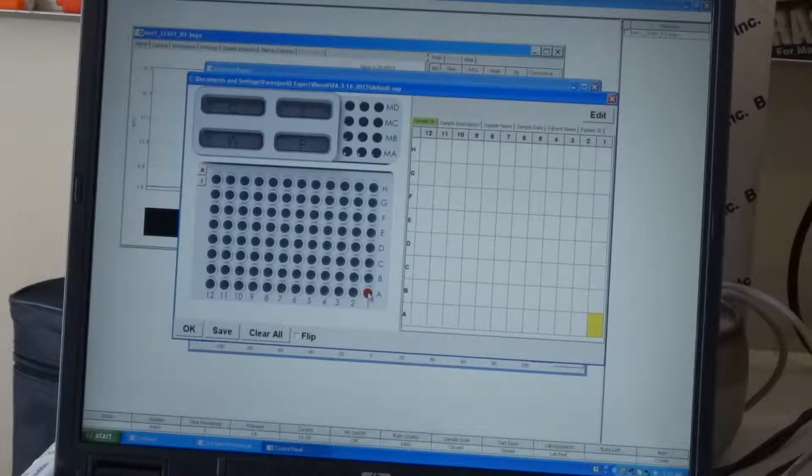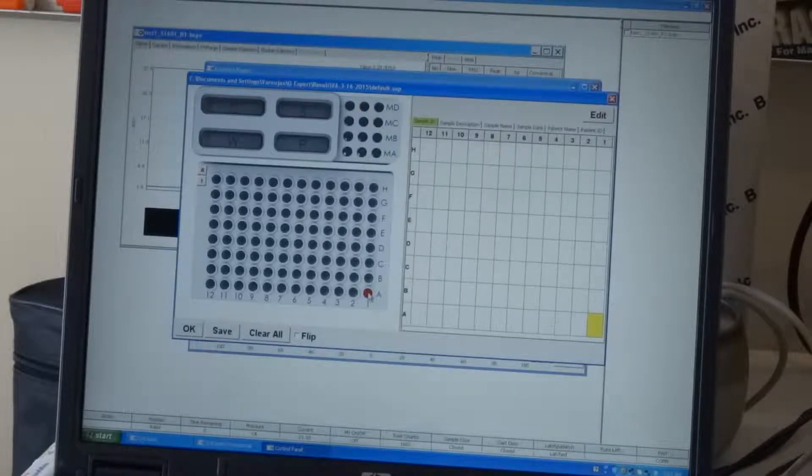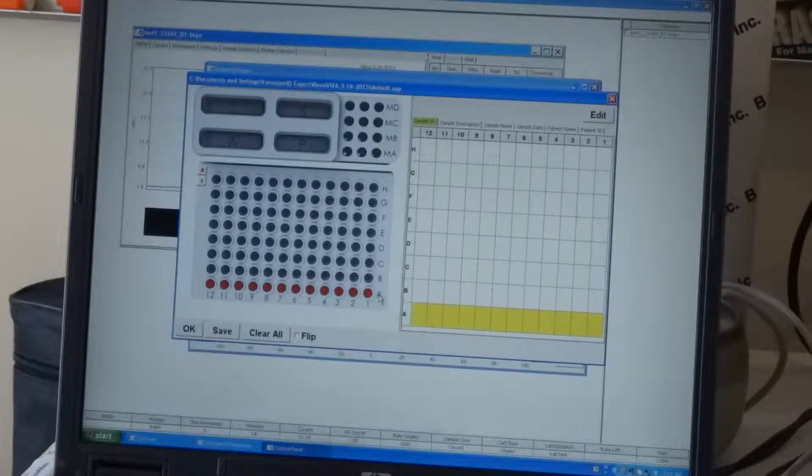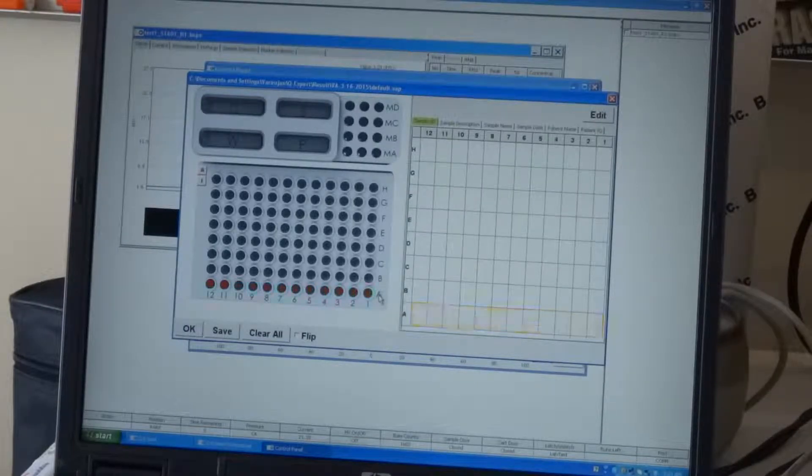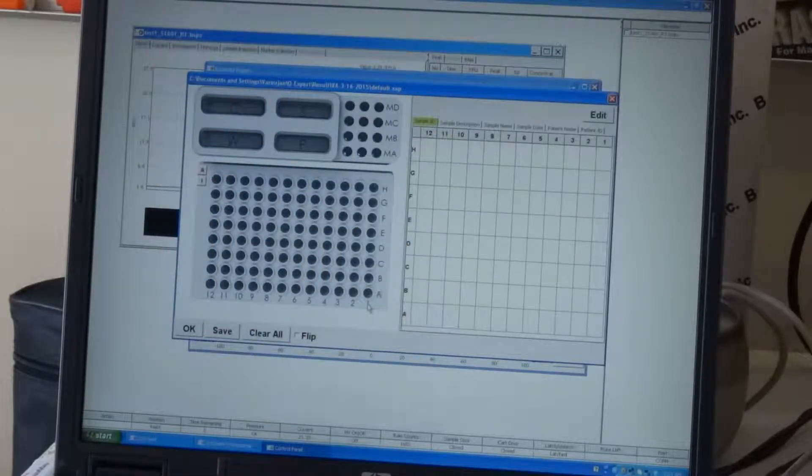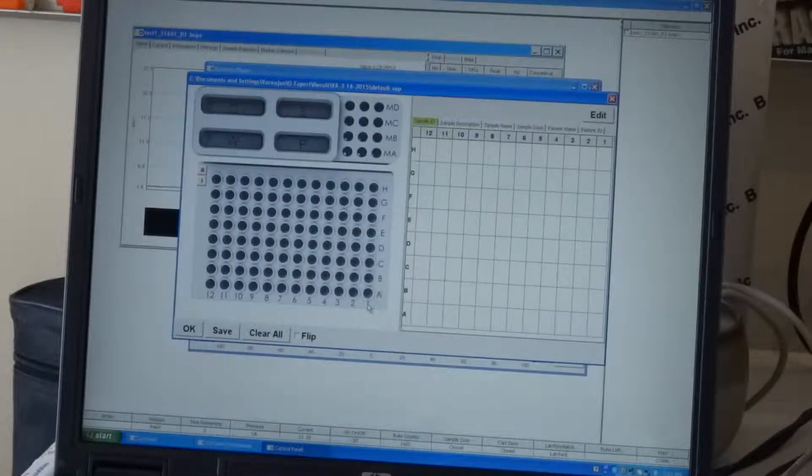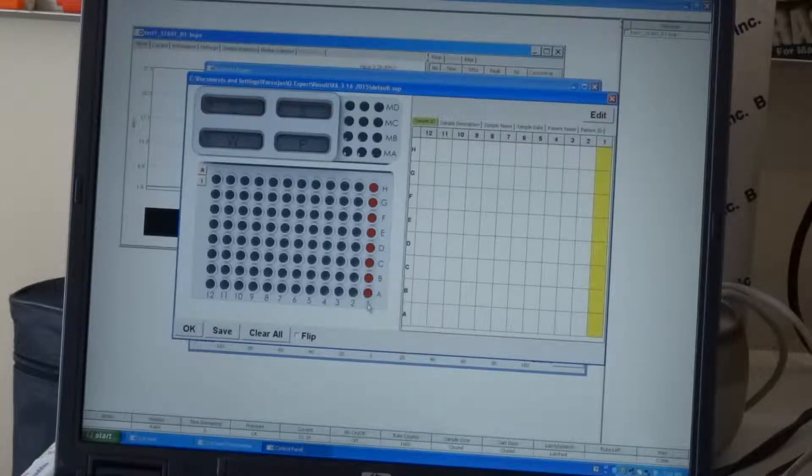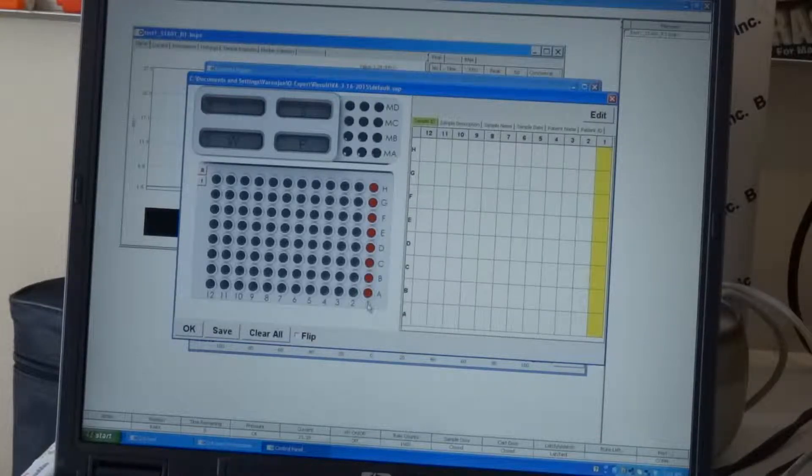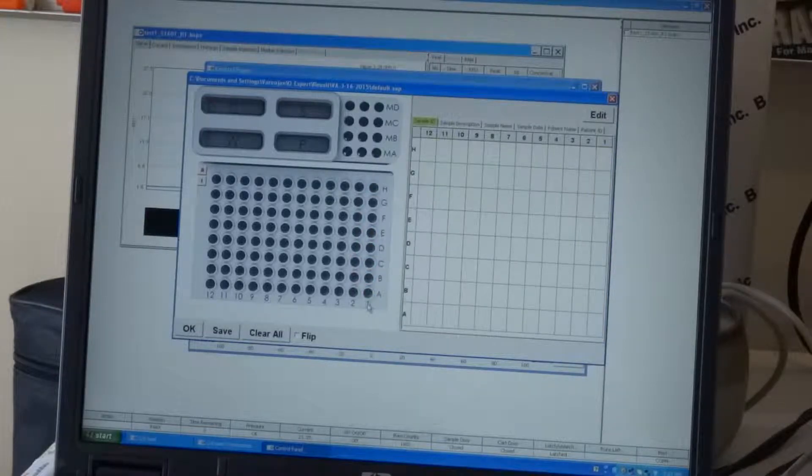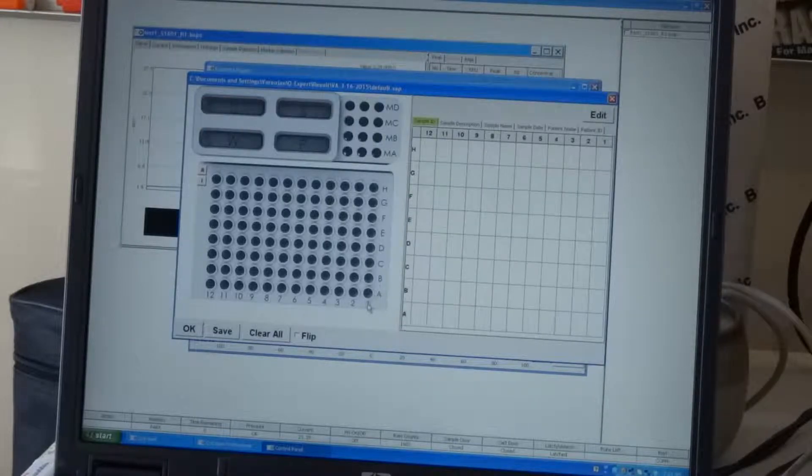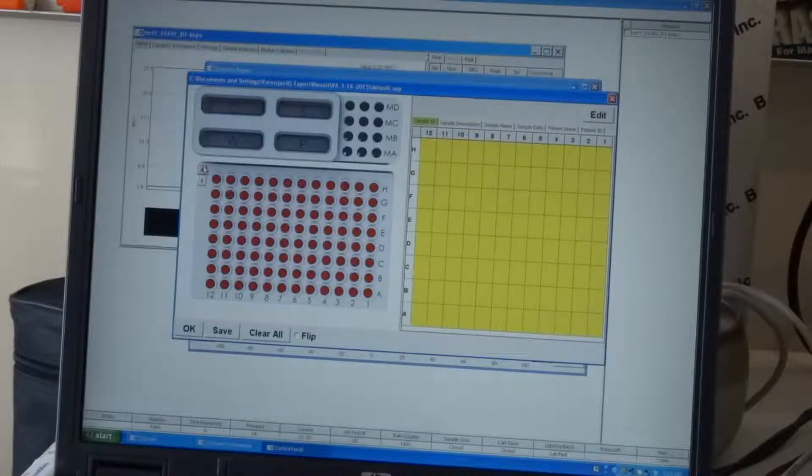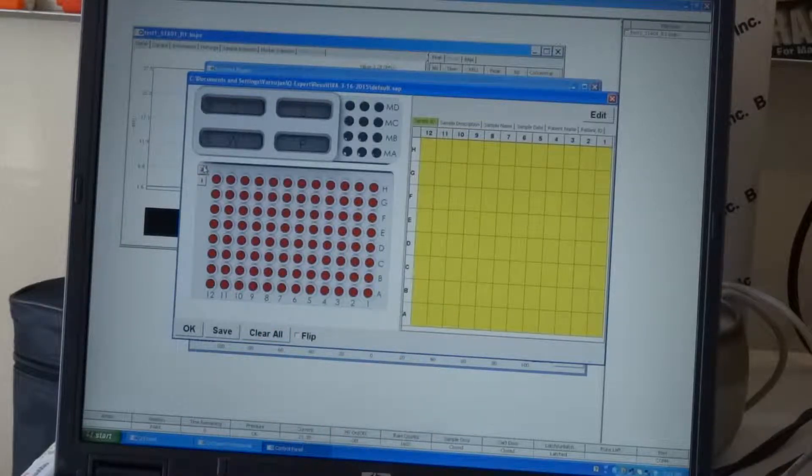But if you have some other samples, let's say you want to run a row of PCR products, if you have a 12-well strip, you will select the 12-well strip by hitting the A. Or, if you want to go A to H, putting eight sample runs, it will select A to H. And if you want to use a 96-well sample tray, it will select all the positions as designated.